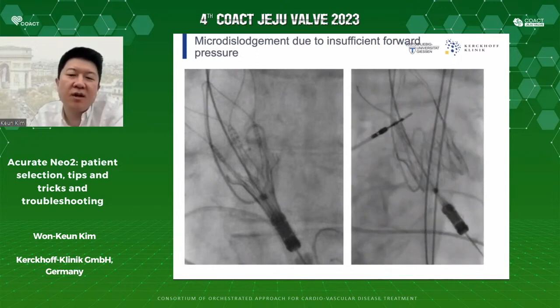If you need some forward push or forward pressure, here you can see what could happen if you don't have sufficient forward pressure. And this is very difficult to measure, actually. And here on the left-hand side, you see appropriate push. You can see that the delivery system is in the outer curvature, and the stent holder moves to the LV after deployment. On the right-hand side, you see what happens if you push too much. This is a very hard push. And actually, this is also very difficult, but it's possible.